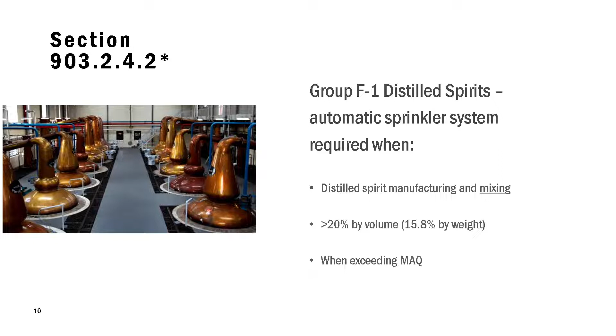But from research and kind of what was going on in the industry, Group F-1 distilled spirits automatic sprinkler requirement. We amended that to clarify and expand on that. So distilled spirit manufacturing and mixing, if it's greater than 20% by volume, and when it exceeds the MAQ, is when we're going to require sprinklers for those types of situations.